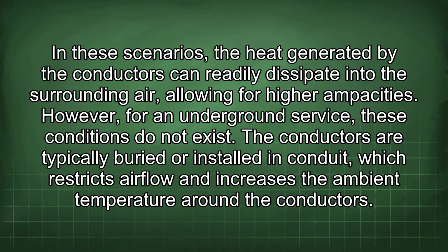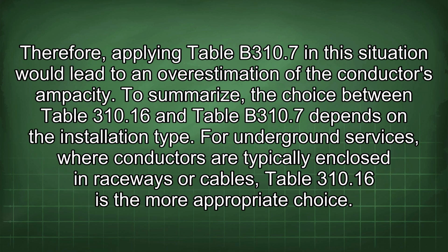However, for an underground service, these conditions do not exist. The conductors are typically buried or installed in conduit, which restricts airflow and increases the ambient temperature around the conductors. Therefore, applying Table B310.7 in this situation would lead to an overestimation of the conductor's ampacity.